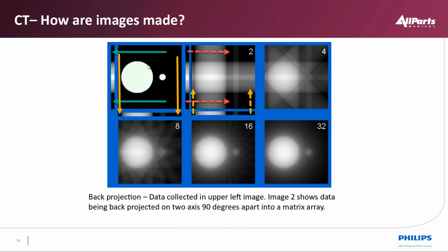Now, the next view, which is where it shows number 2 up there, would be in a computer matrix, taking the raw data that we received off this scan and then back projecting from 2 different angles, 90 degrees opposed to each other. And that would build up this representing that image in completed recon data. As we add more and more views or samples, depending on the OEM, we will then build up more and more of the image, where you have 8 and then 16 and then 32.